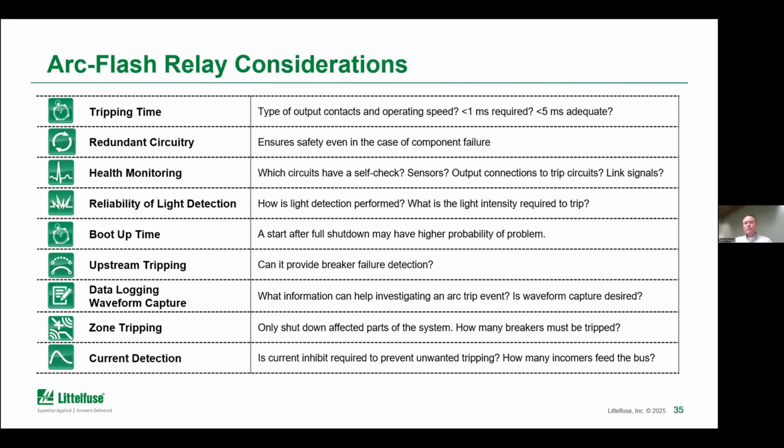Another is, what are the safety functions of this relay? So I show redundant circuitry here. So whether the device is using redundant circuitry to provide that safety, that solid performance when it comes to the analysis of the product under component failure. Is it SIL rated? What are those things in terms of the redundant circuitry and safety for this product?